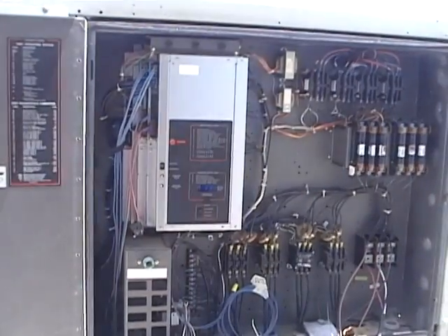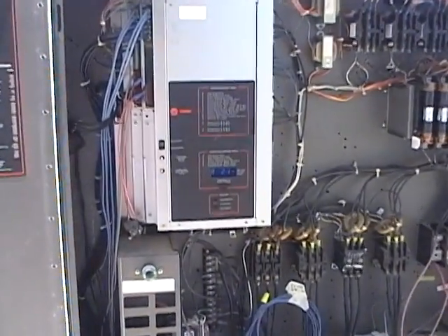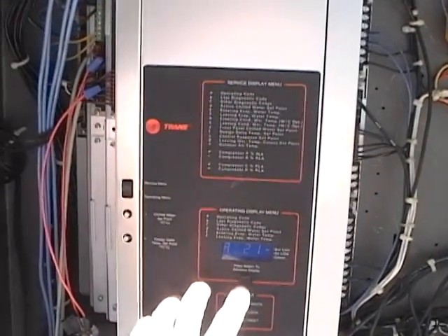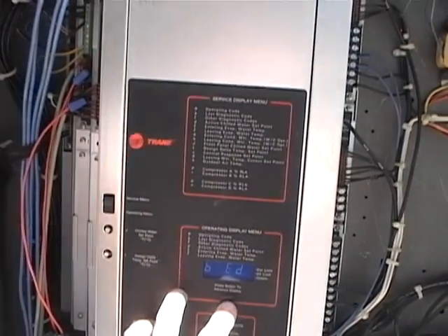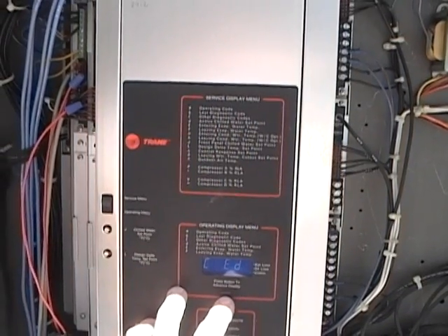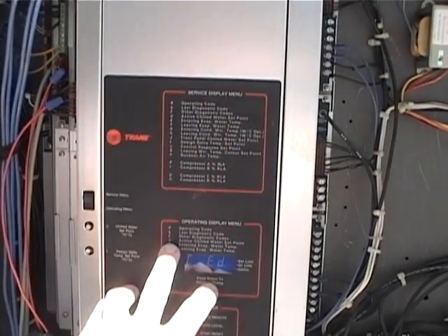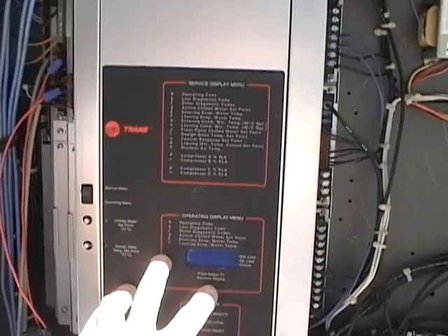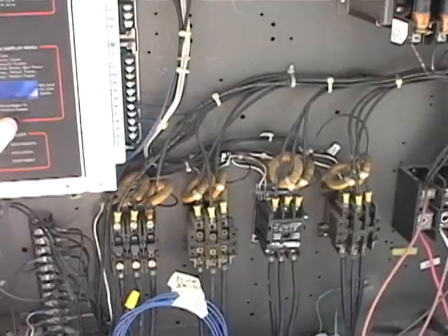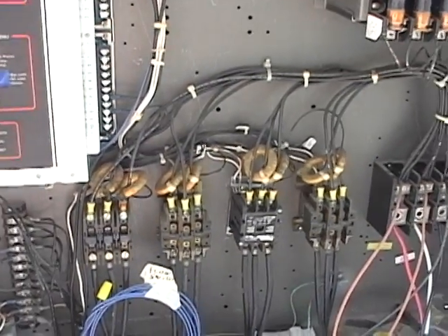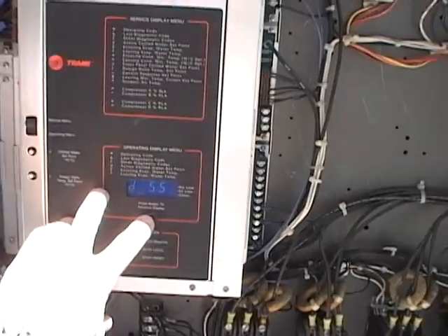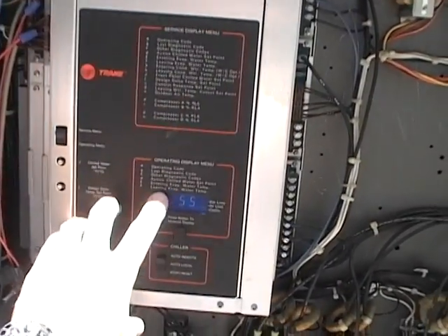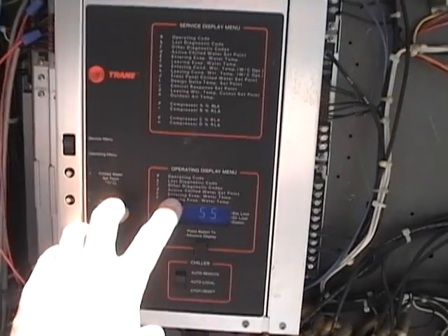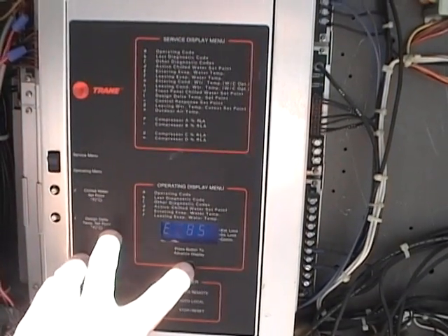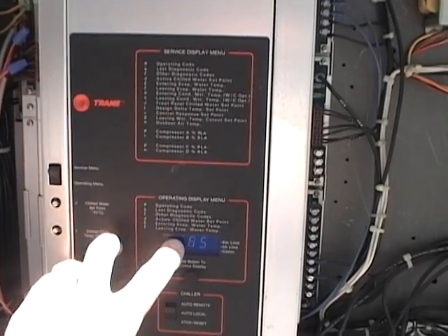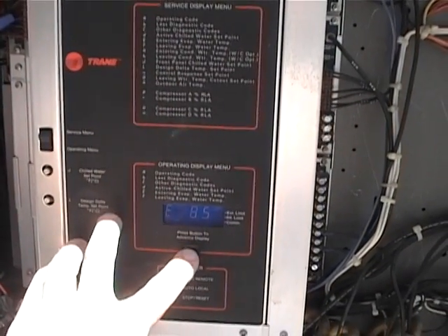Here we go, the unit just turned on, and we'll show you some of the functions we have over here. E is incoming temperature. It just pulled in a second compressor. I don't know if you heard that or not. She wasn't quite happy with cooling down quick enough. So D is your set point. D is the set point. E is the temperature coming in. This is the temperature of the water coming in.